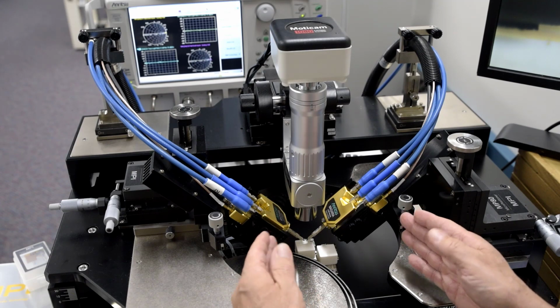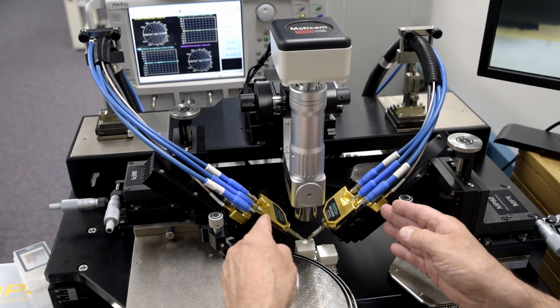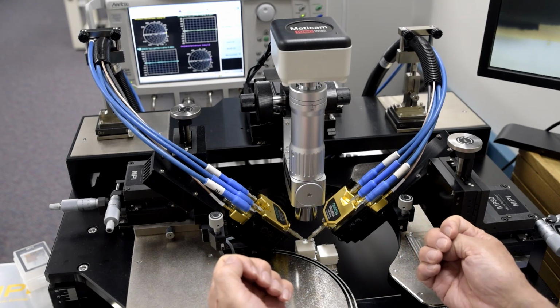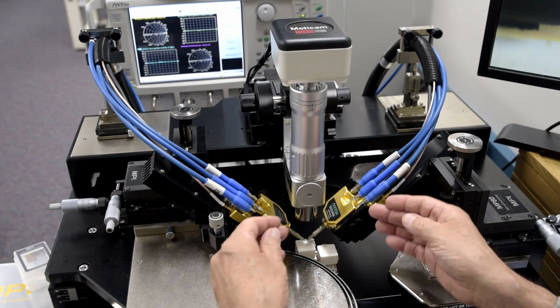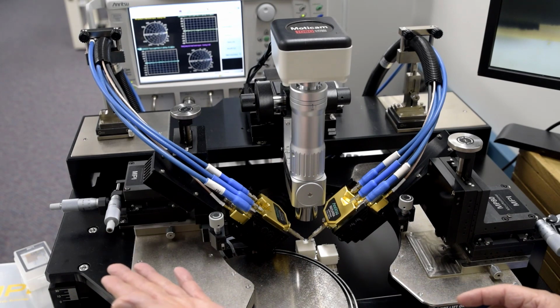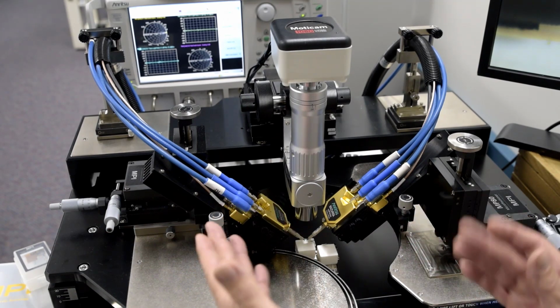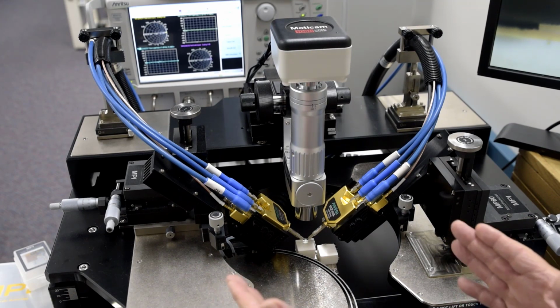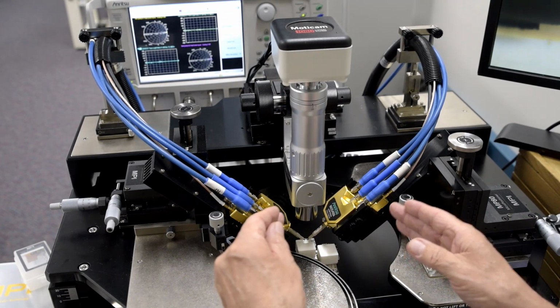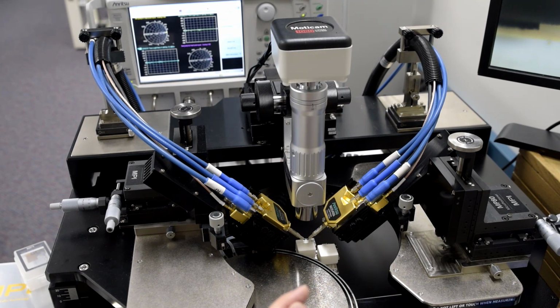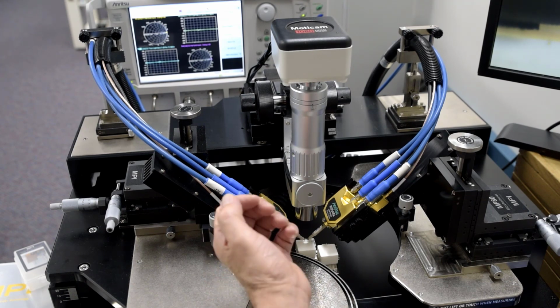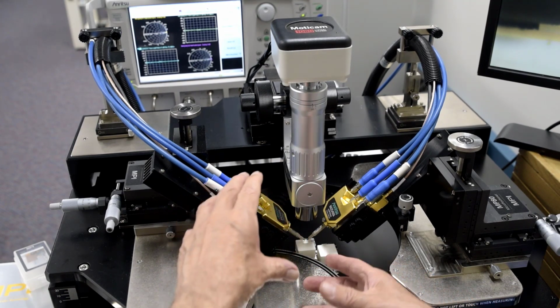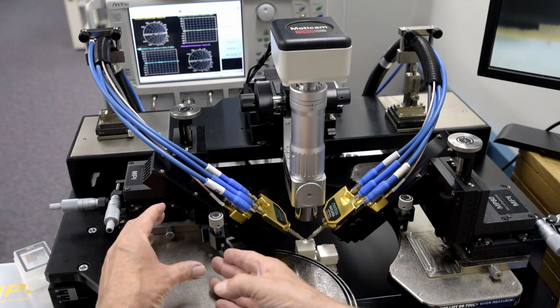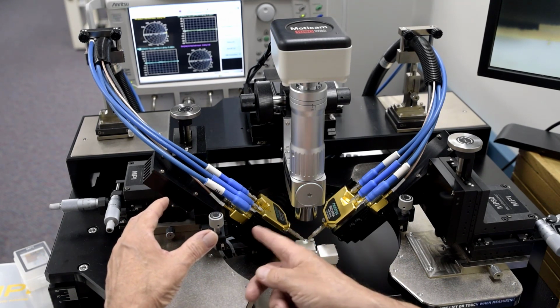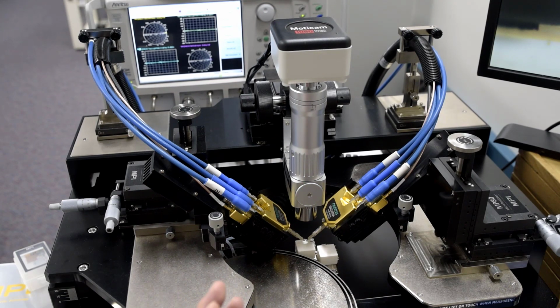But the key point is, because the nonlinear transmission line modules are small and compact enough, we're able to mount those modules directly to the probes, whether it's a 110, a 125, 145, or the 220 gigahertz system. That's always been a key objective, is to be able to remove and eliminate the need for test port cables between the probes and the modules. If the modules are too large to mount directly, then what you'll need to do is move the modules back onto the platen and connect to the probe using cables.